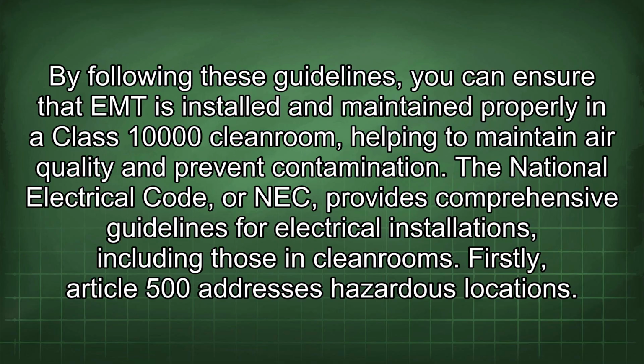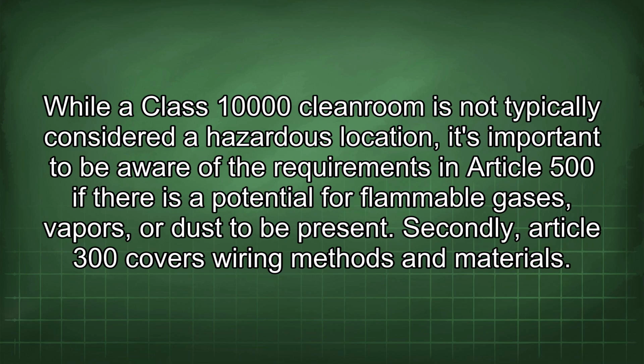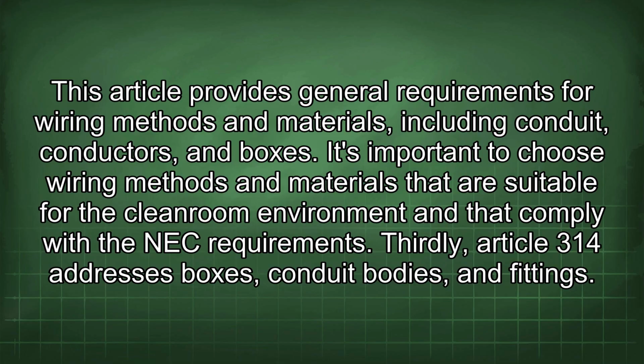The National Electrical Code, or NEC, provides comprehensive guidelines for electrical installations, including those in cleanrooms. Firstly, Article 500 addresses hazardous locations. While a Class 10,000 cleanroom is not typically considered a hazardous location, it's important to be aware of the requirements in Article 500 if there is a potential for flammable gases, vapors, or dust to be present. Secondly, Article 300 covers wiring methods and materials. This article provides general requirements for wiring methods and materials, including conduit, conductors, and boxes.